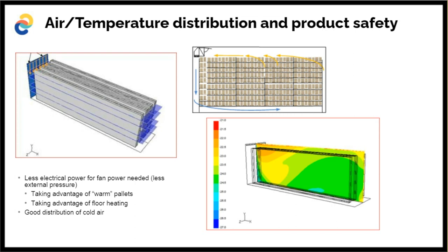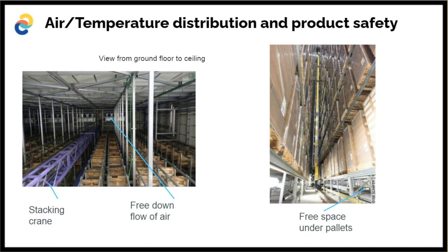And for that, we are using these CFD calculations to make sure to the customer that all the temperatures in this room are within the range. So it's a very nice system with a relatively low absorbed power of the fans, and a nice even distribution of temperatures. Of course, it's not always possible to do that. Your cold store needs to be suitable for that. You need to be able to have a free downflow of air.